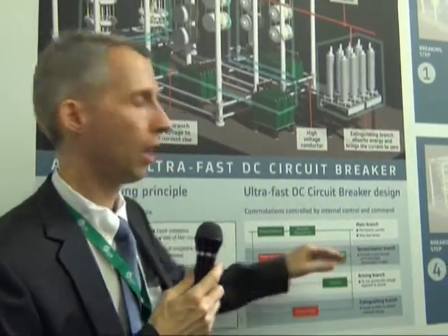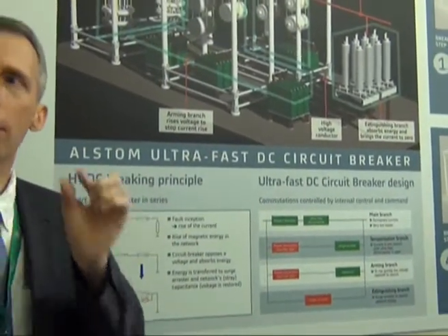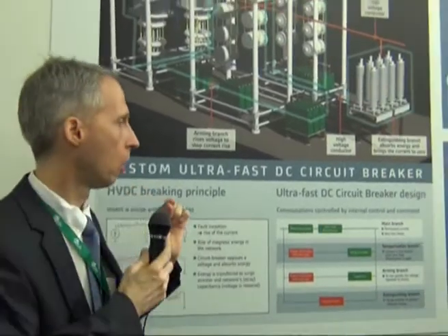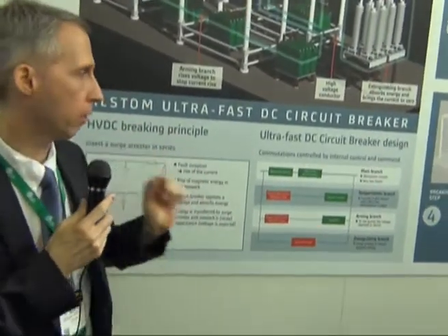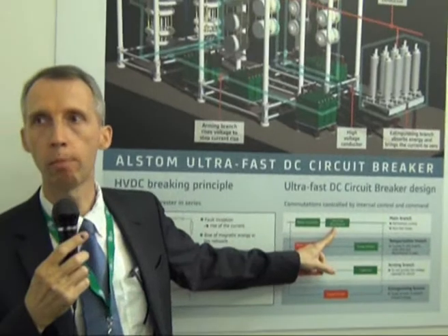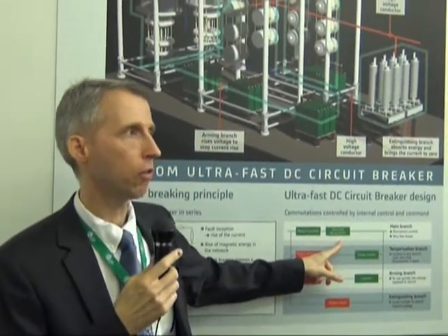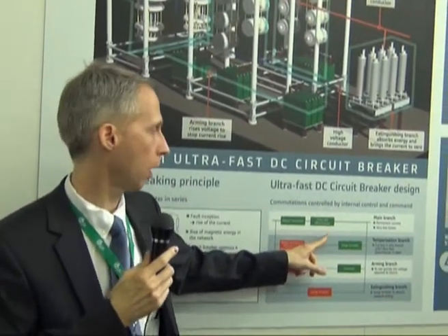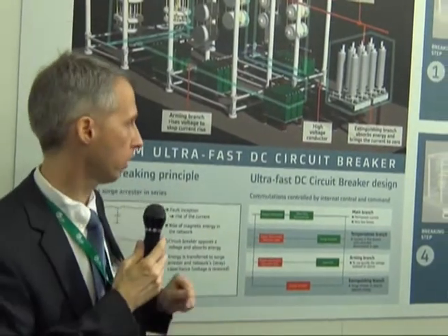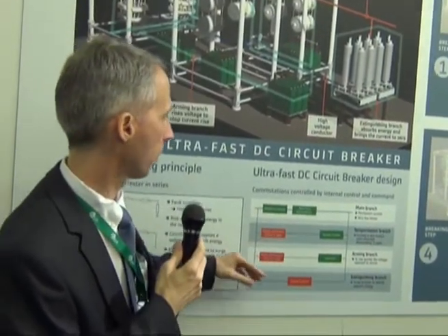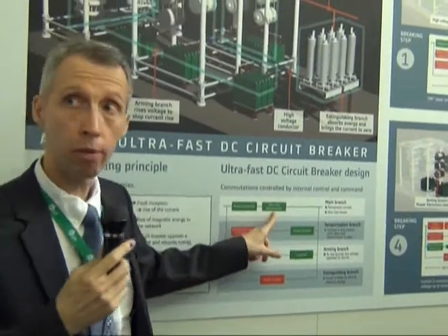So from outside we will see that this here is as if nothing happened, but only for a very short amount of time. Only for the amount of time necessary for this disconnector to open. And we will see that this is the key. This is the key for DC interruption. I'll show it later.